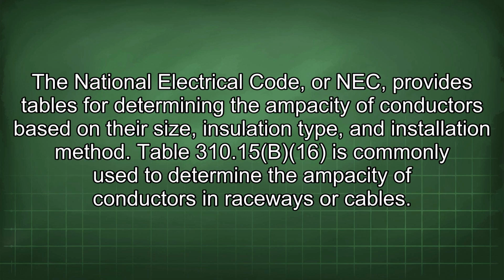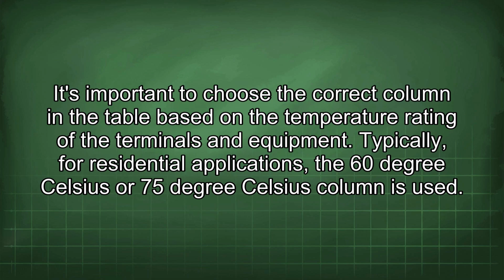The National Electrical Code, or NEC, provides tables for determining the ampacity of conductors based on their size, insulation type, and installation method. Table 310.15(B)(16) is commonly used to determine the ampacity of conductors in raceways or cables. It's important to choose the correct column in the table based on the temperature rating of the terminals and equipment. Typically for residential applications, the 60 degrees Celsius or 75 degrees Celsius column is used.